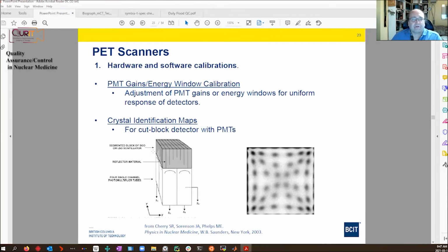So the calibrations involved depend on the technology. If the PET scanner does not use PMTs, this isn't relevant, but if it does use PMTs, the PMT gains and the energy windows have to be calibrated, sort of calibrating the energy scale, and the PMT gains have to be adjusted so that they're consistent throughout the camera. Otherwise, you're going to get some variations in the efficiency of detector pairs. In cameras that use this block crystal design, where you have 4 PMTs, but in this particular example, I think it's 64 cuts here.